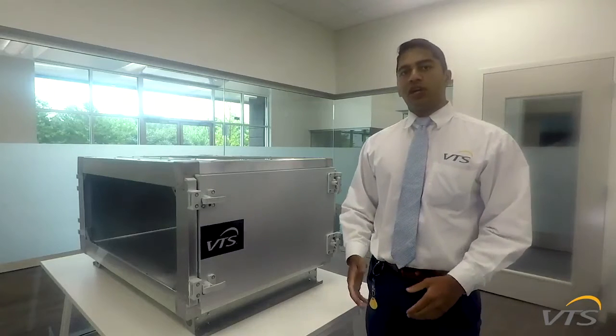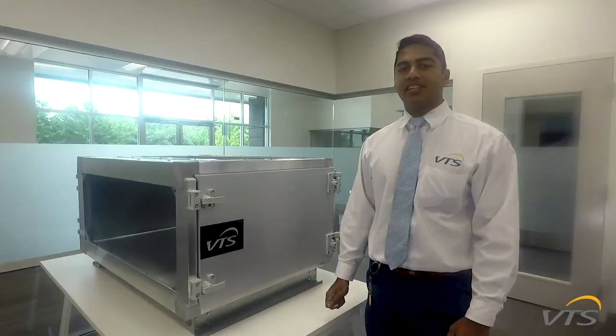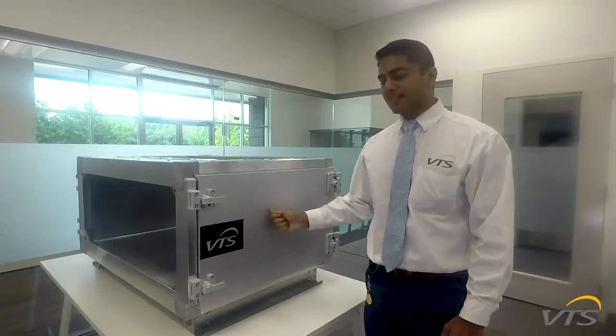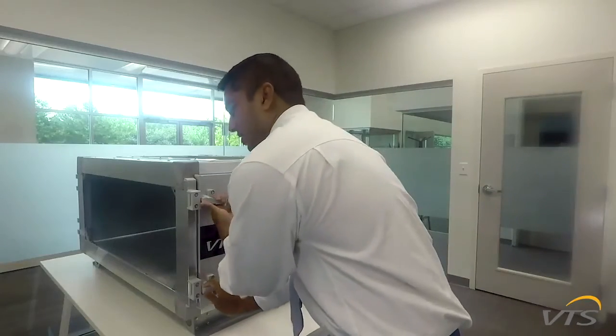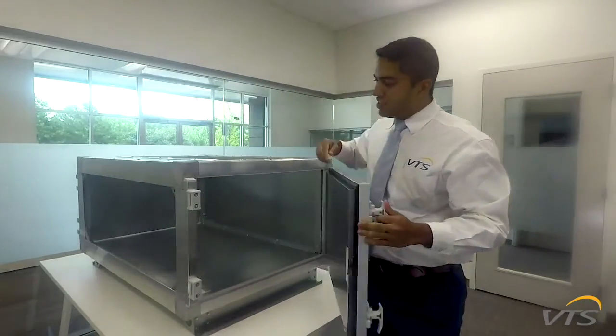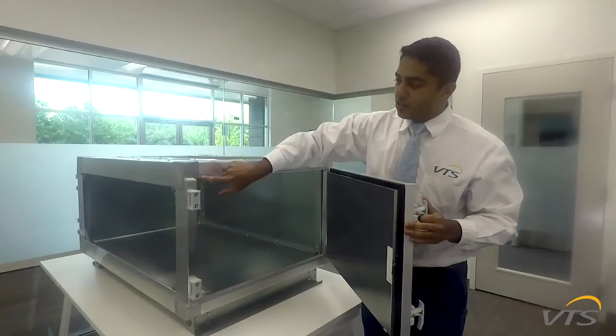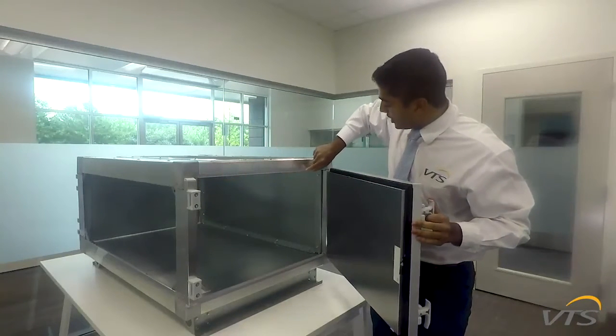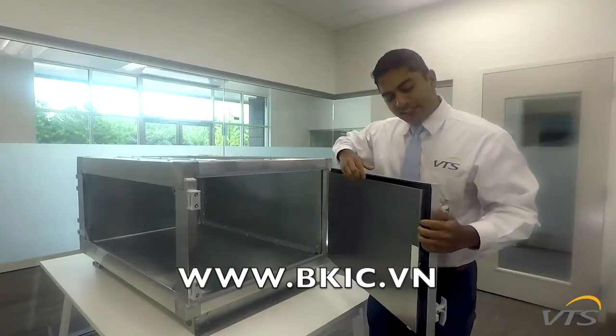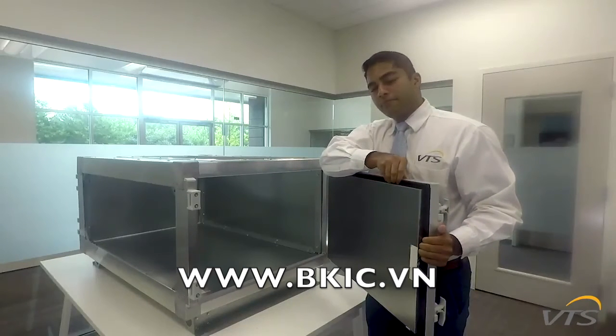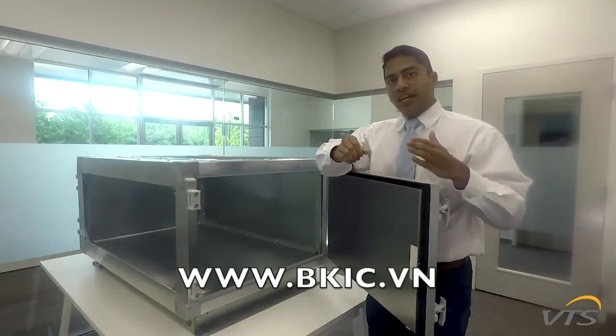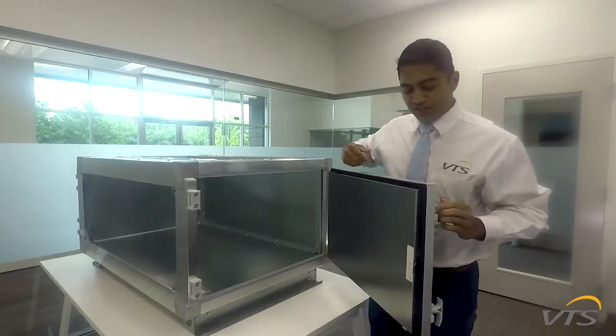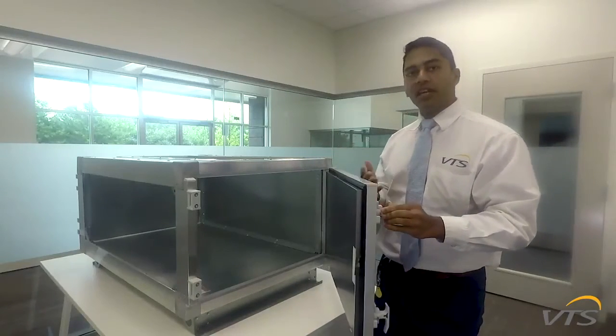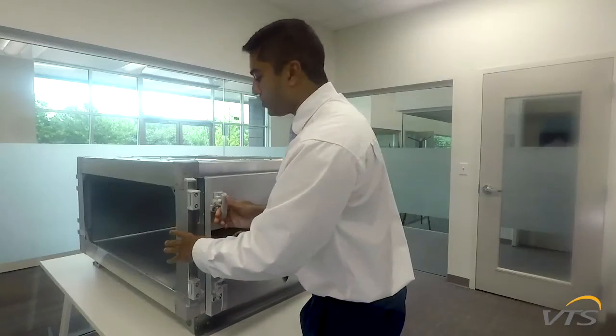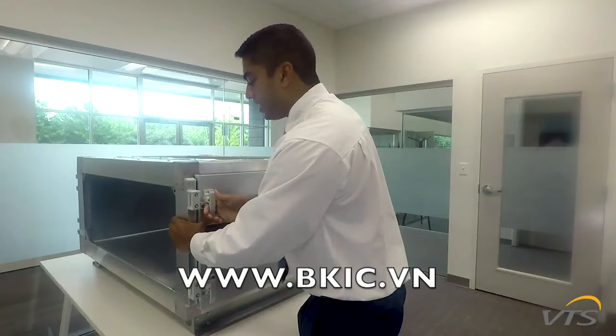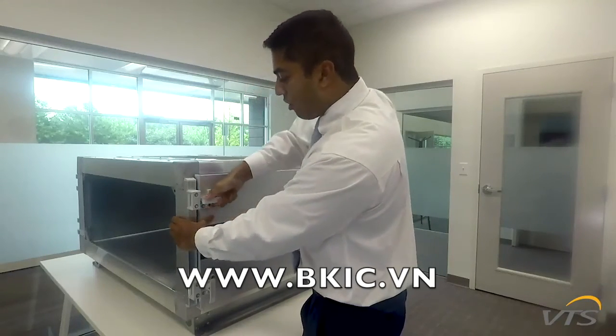Another way we try to minimize any points where air leakage can occur on these units is with the access door. If we take a closer look, as you can see, we provide a knife edge seal along the full perimeter of each of the access doors. And this fits into this ribbed gasketing, and that way we ensure, again, minimal points where air leakage can occur in this unit. And on the opposite end, showing the closing of the door, we see the compression of the gasketing on all 4 points.